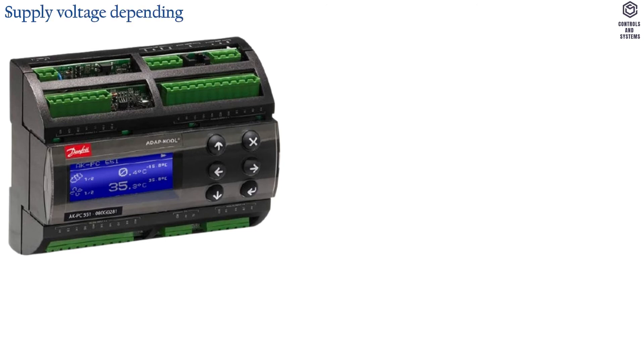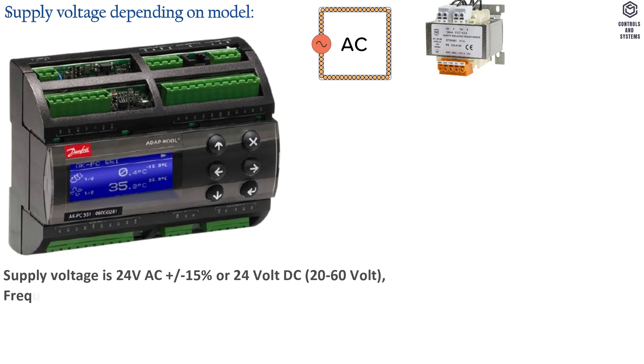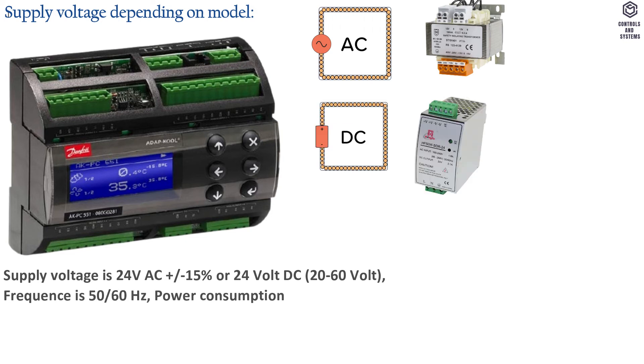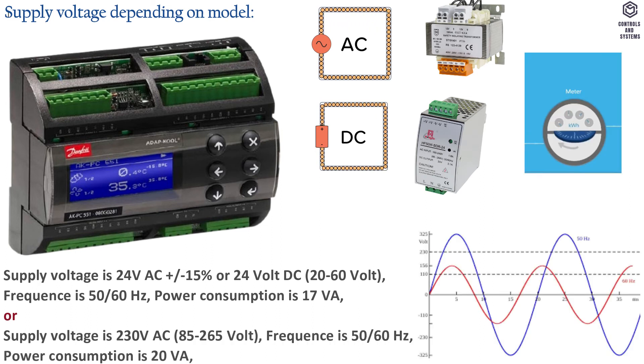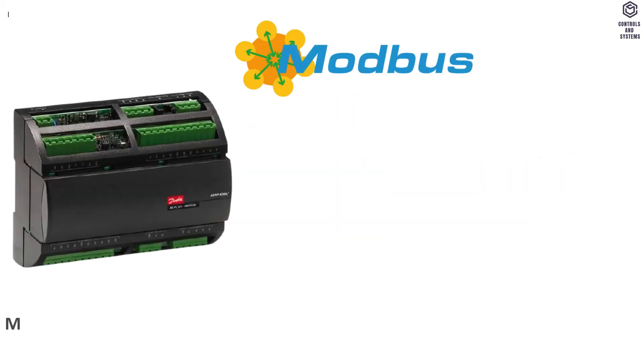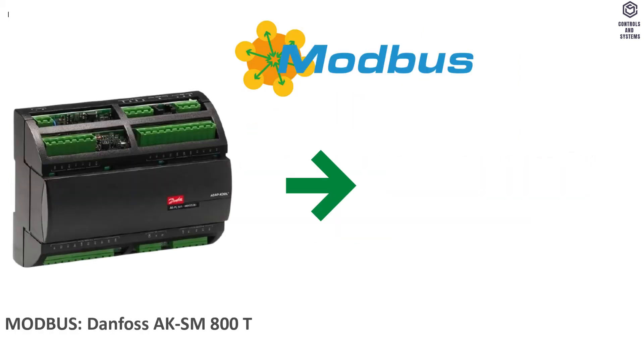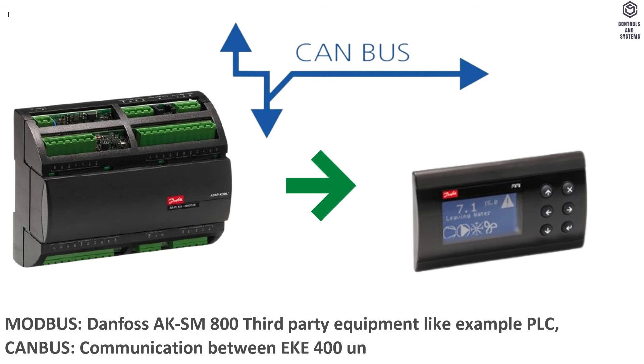Electrical data: supply voltage, depending on model, is 24V AC ±15% or 24V DC, 20 to 60 volts; frequency is 50 or 60 Hz; power consumption is 17 VA. Data communication: Modbus for Danfoss AK-SM800 and third-party equipment such as PLCs; CAN bus for communication between EKE400 units and HMI.